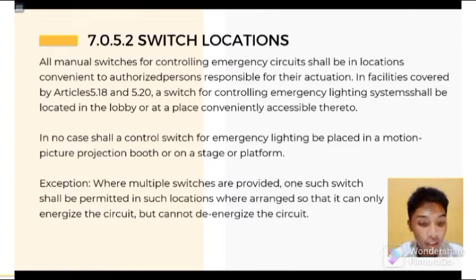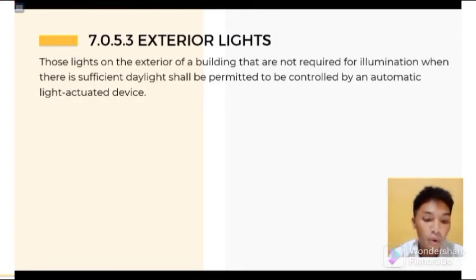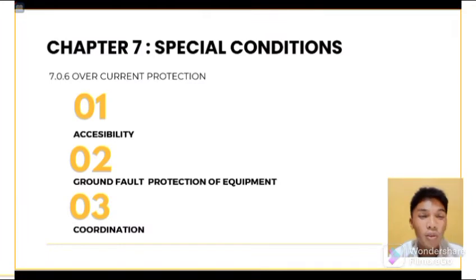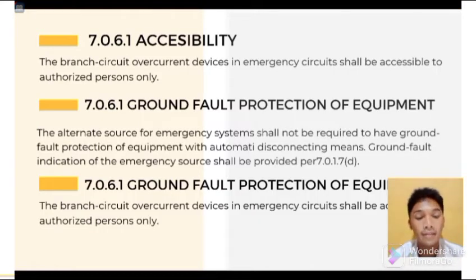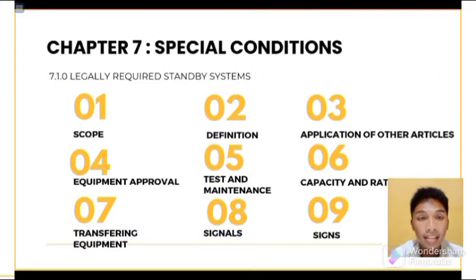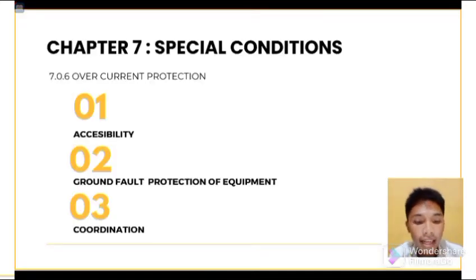Next is the overcurrent protection. Accessibility. The branch circuit overcurrent device in emergency circuits shall be accessible to authorized persons only. Ground fault protection of equipment. The alternate source for emergency system shall not be required to have ground fault protection of equipment with automatic disconnecting means. Ground fault indication of the emergency source shall be provided as discussed in 7.0.1.7 letter D. So 7.0.6.3 coordination, emergency system or systems overcurrent devices shall be selectively coordinated with all supply side overcurrent protective devices.